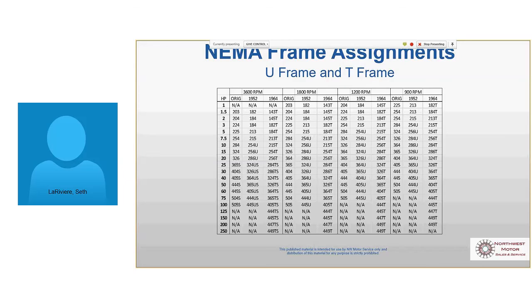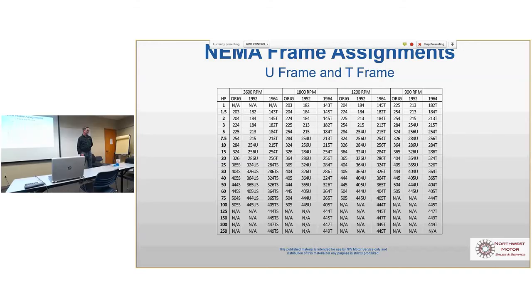Almost everything you see in the field is going to be a T-frame motor. Let's talk about what the frame means and some of the problems we see with guys. We'll get a call, right, and somebody's installing a motor, and we'll pick 10 horse 1800 again. So they've got a 215T motor, and we'll get a call, and it doesn't fit. Well, a 215T is going to be the same across all the manufacturers in some cases. Your bolt hole pattern for the feet is going to be the same, shaft height, shaft diameter, usable shaft length.